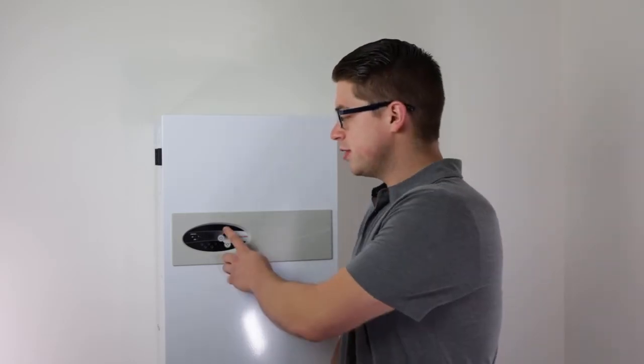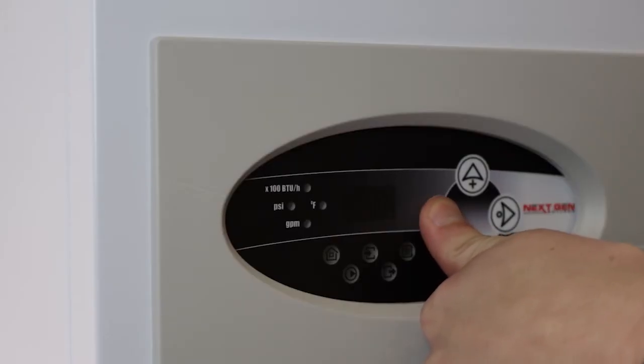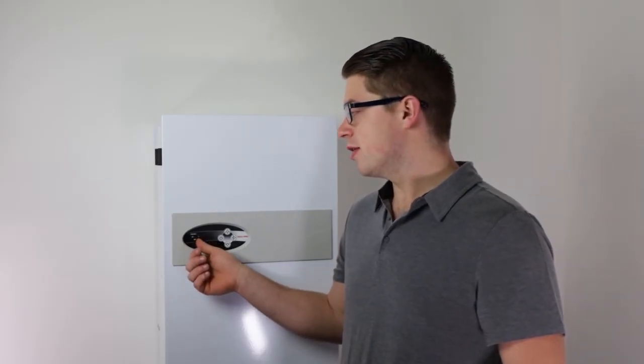Now we're going to talk about turning your NextGen boiler into standby or summer mode. Detailed instructions on how to do so can be found on page 13 of the installation manual. To switch your NextGen boiler into standby mode, you want to press and hold the power button for 3 seconds. Once you have done so, a red indicator light on the control panel will start flashing.